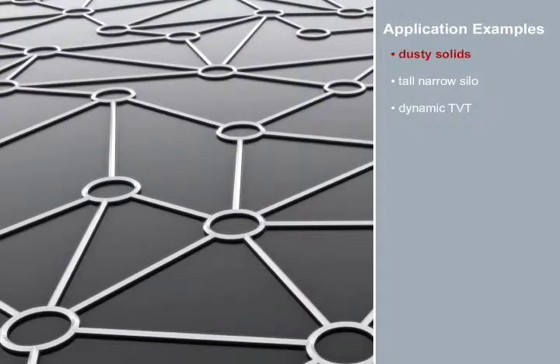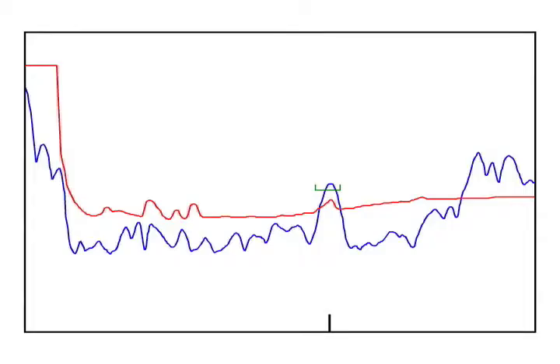Application 1, Dusty Solids. This echo is from a Siemens LR460 monitoring a very dusty solids application in the food industry. When we first looked at this echo profile, we saw a nice little echo right here. This was exciting because we were told that this would be a really difficult application.